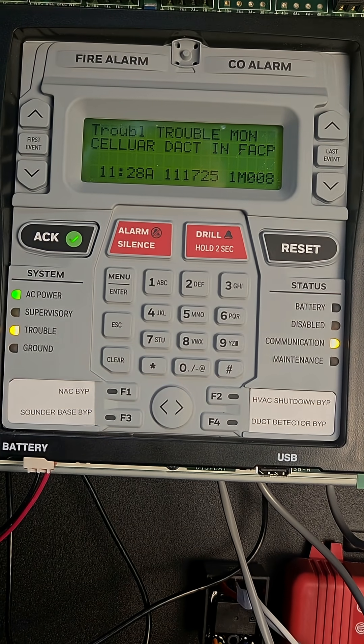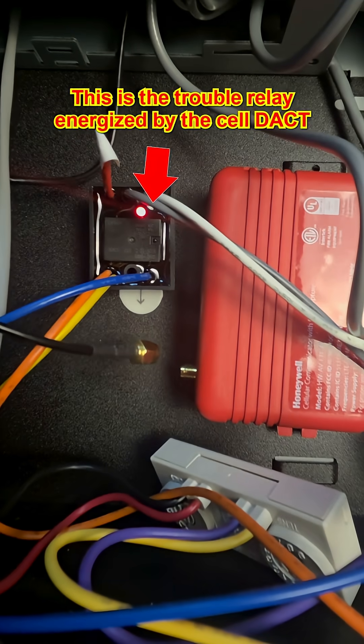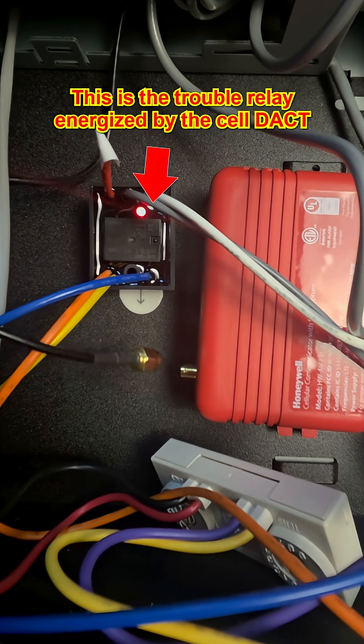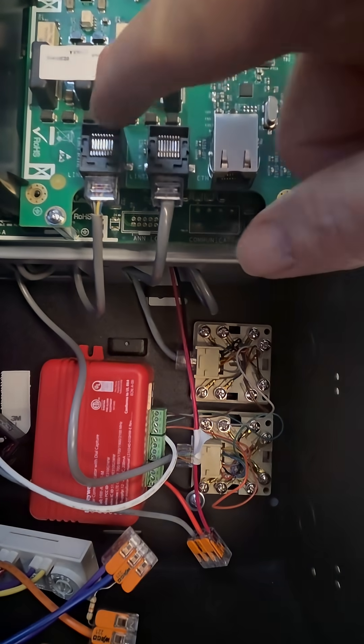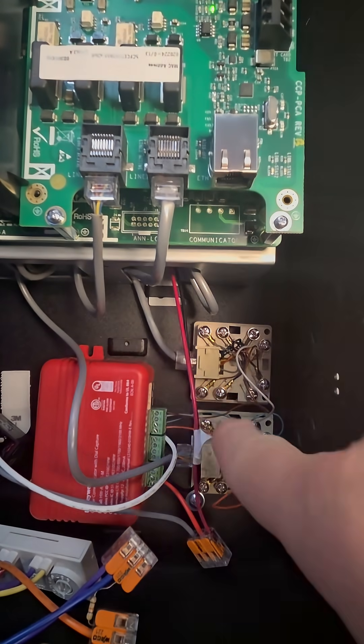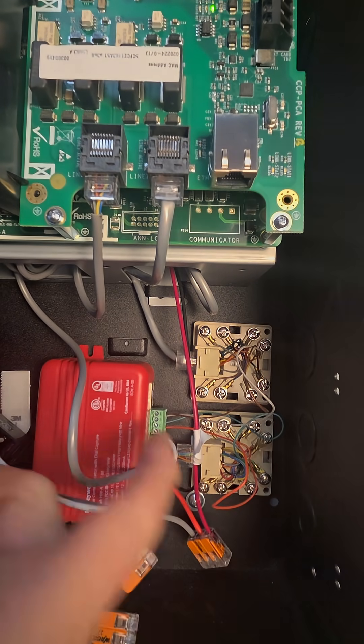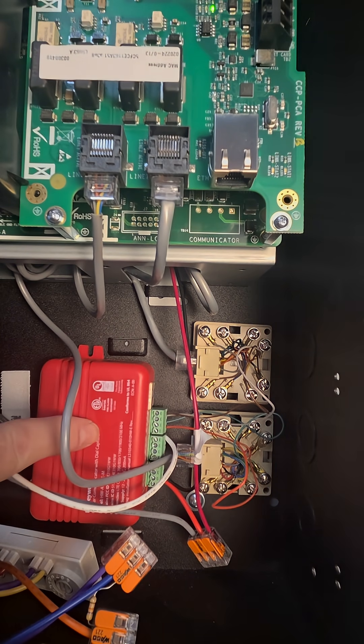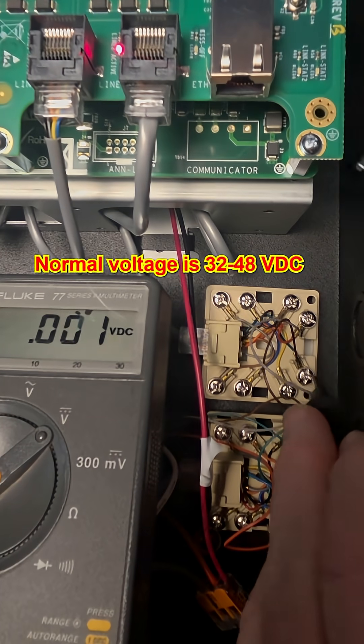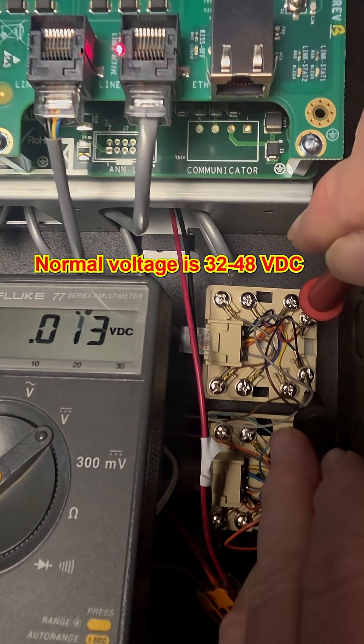We have a trouble on our Notifier 50X because we've disconnected the antenna on the cellular DACT. With the antenna disconnected, the DACT cannot get cellular service. The internal communicator is connected via these cables to these jacks, and it's the cellular communicator here that generates phone line voltage. Without service, the cell DACT will drop the voltage on these terminals so they're zero.